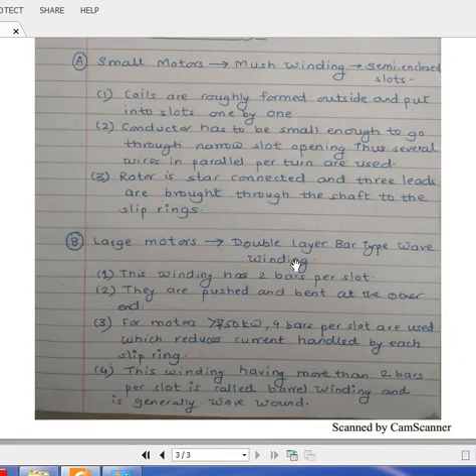For large motors, you are going to use double layer bar type wave winding. So this winding generally has two bars per slot and they are pushed and bent at other end. For large motors, because this is bar type winding, sometimes for motors which are greater than 750 kilowatt, your bars will be more than two - four bars per slot are used. And because your bars are going to increase, your current handled by each slip ring is reduced.